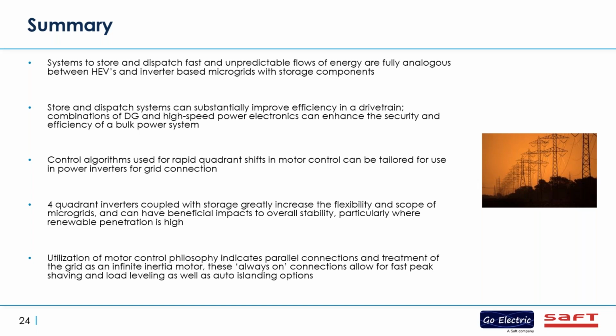Control algorithms used for rapid quadrant shift and motor control can be tailored for use in power inverters and grid connections. A 4-quadrant grid power inverter coupled with storage can greatly increase the flexibility and scope of a microgrid, and can have a beneficial impact on overall stability, particularly where renewable penetration is high, or as in the case of this installation, renewable penetration is 100%.